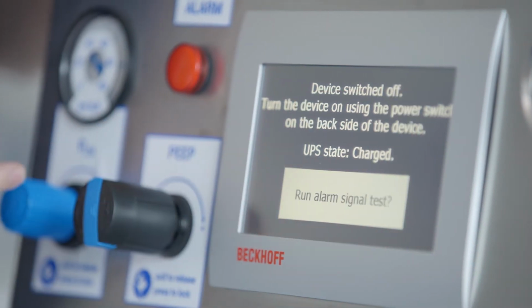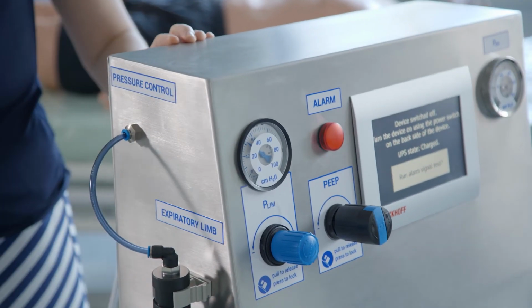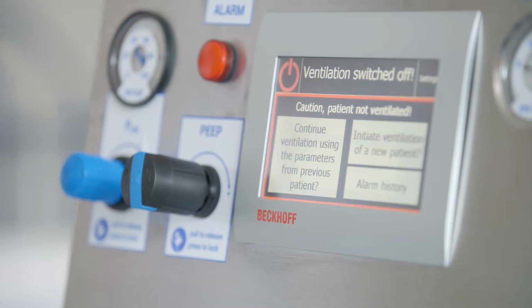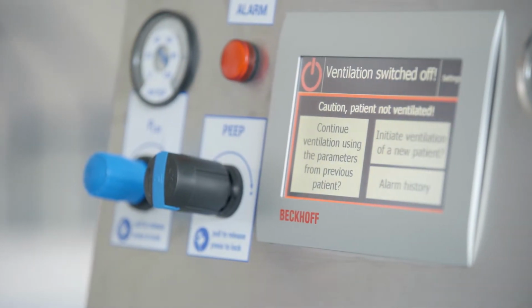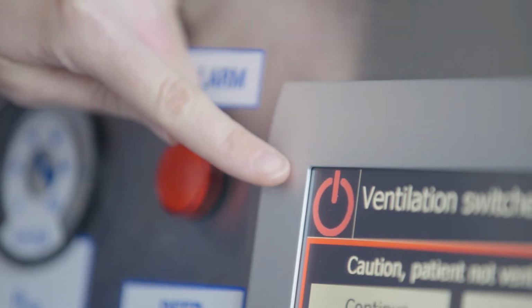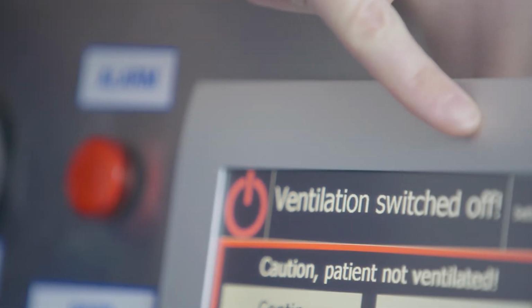Now we can switch on the ventilator using the on-off button at the back of the panel. The ventilator is now in standby. In standby, the ventilation is off, which is indicated by the red symbol and the text on the screen.